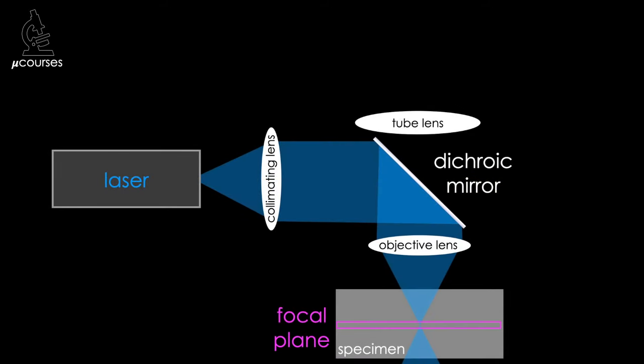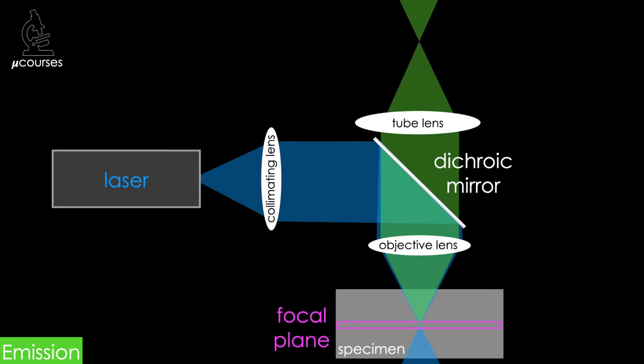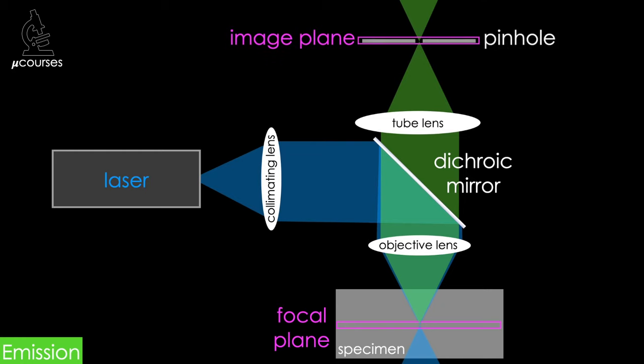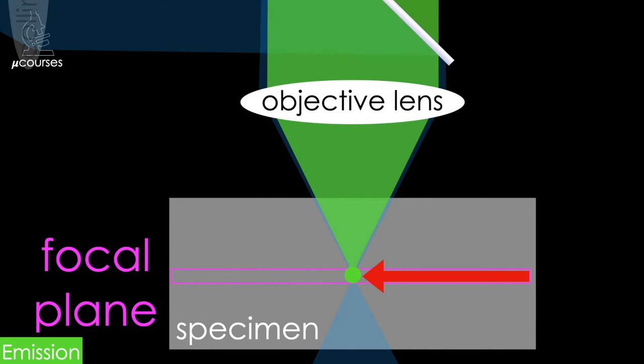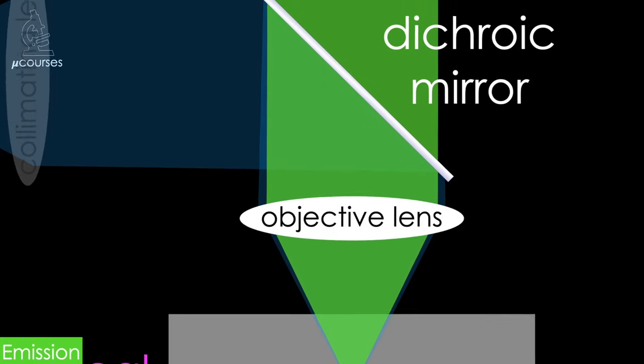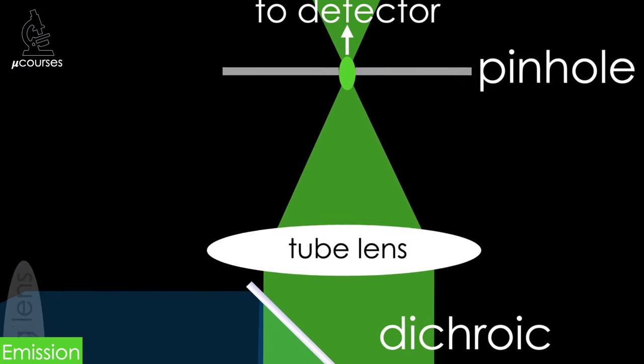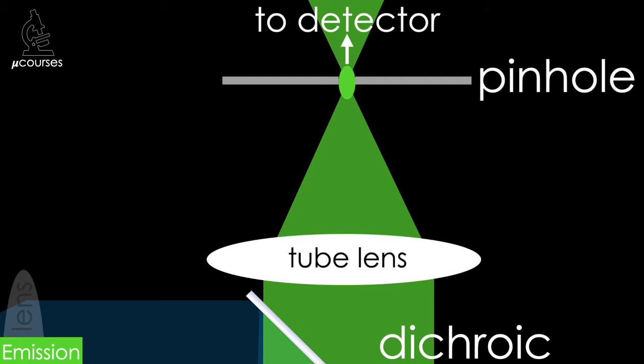Let's go back to our simple diagram of a confocal and look now at the emission light path — the light emitted by the fluorophore in our sample. The image of the sample is focused onto a plane within the microscope called the image plane, and the pinhole resides at this image plane. Fluorescence emitted by objects in the focal plane of the objective lens is collected by the objective lens, passes through the dichroic mirror, and is focused by the tube lens onto the image plane. The pinhole is positioned such that this focused image can pass through to the detector, which collects the emission light photons and is used to generate a digital image of the sample.